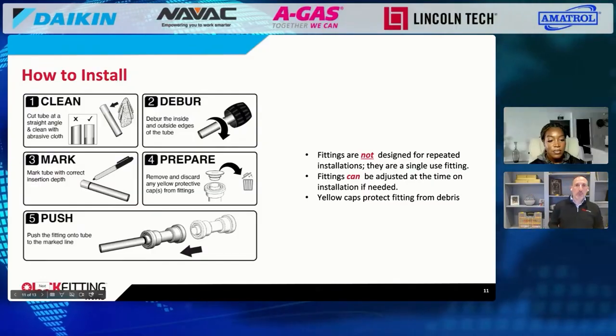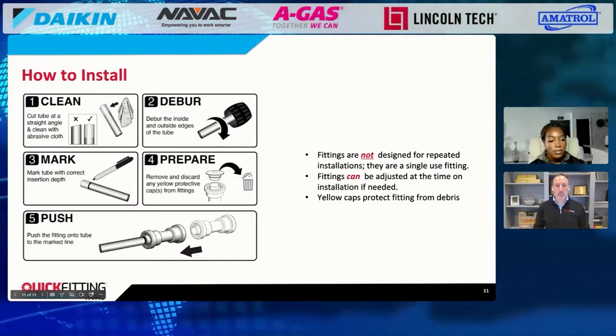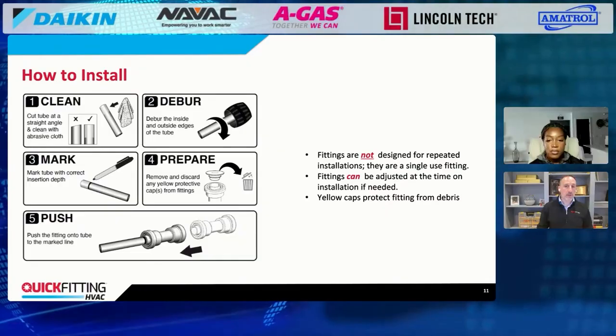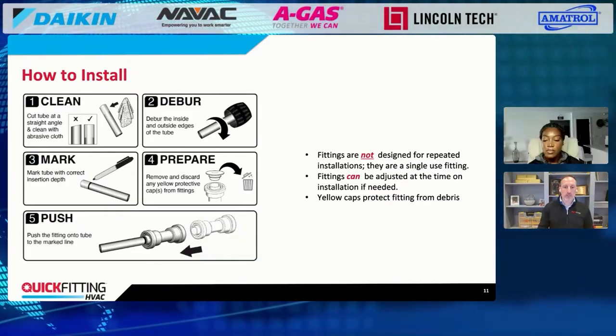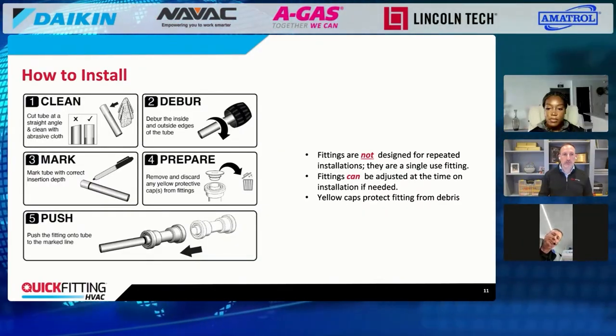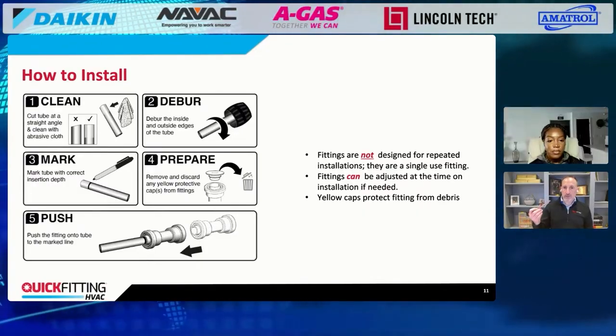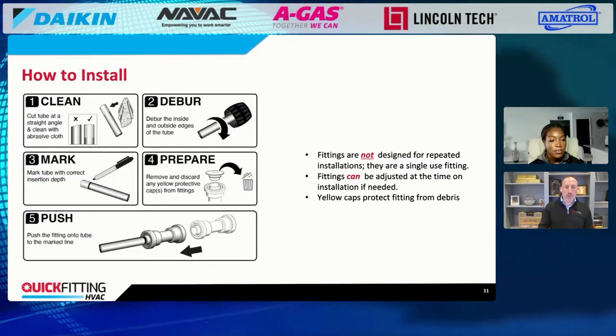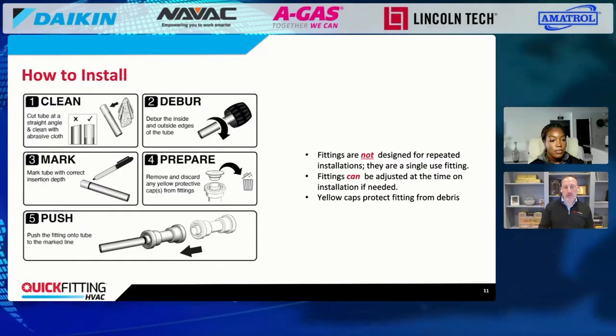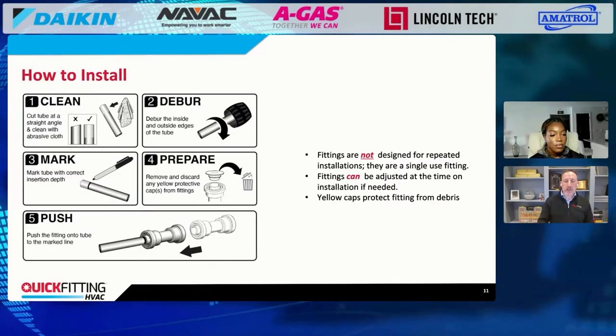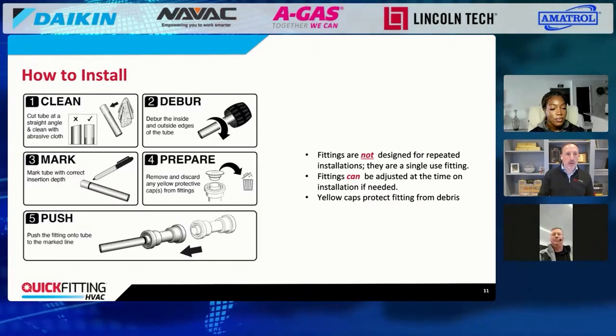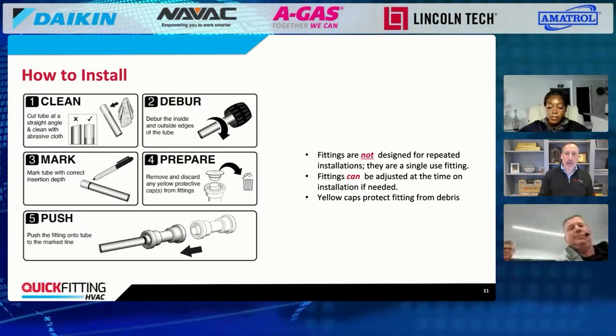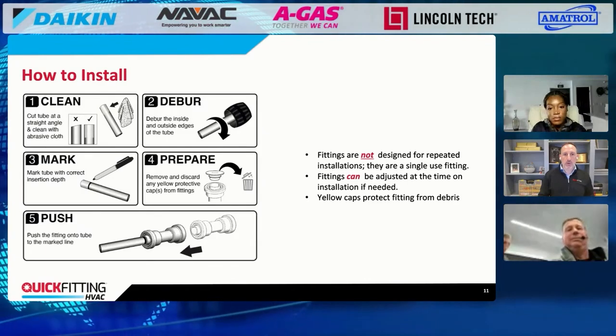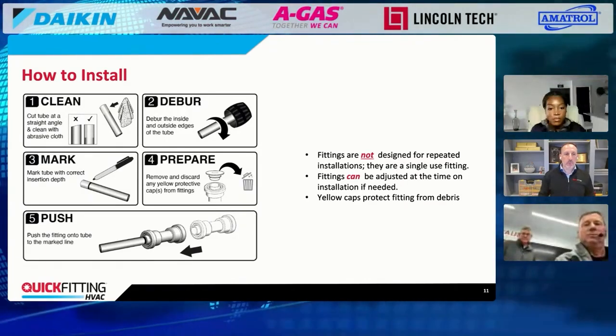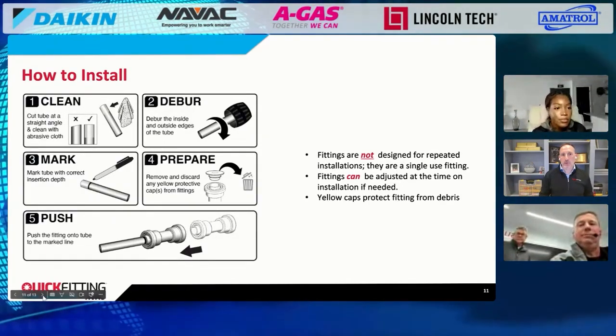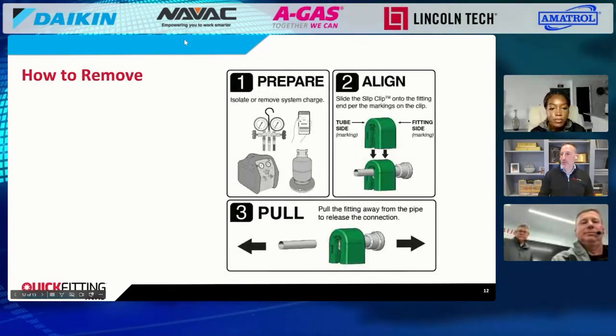The problems you face in the field that we've designed around include vibration, galling, and temperature extremes. These are designed to go down to minus 40 degrees Fahrenheit and up to about 300 degrees Fahrenheit, so a wide range. You could use it outside, even in the north, without worrying about O-ring or fitting degradation. We design them to be very robust for most applications.